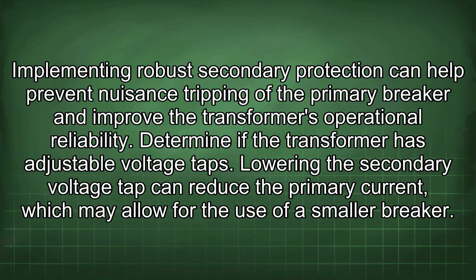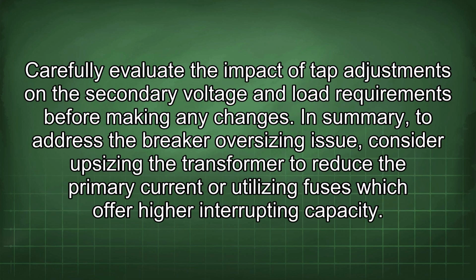Determine if the transformer has adjustable voltage taps. Lowering the secondary voltage tap can reduce the primary current, which may allow for the use of a smaller breaker. Carefully evaluate the impact of tap adjustments on the secondary voltage and load requirements before making any changes.